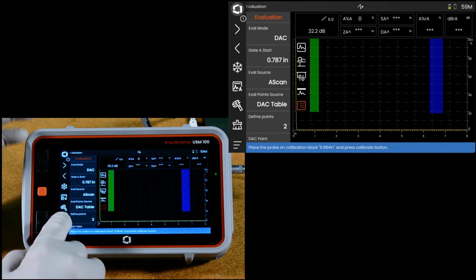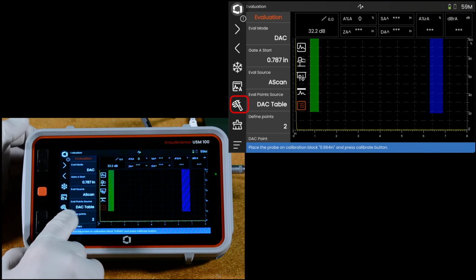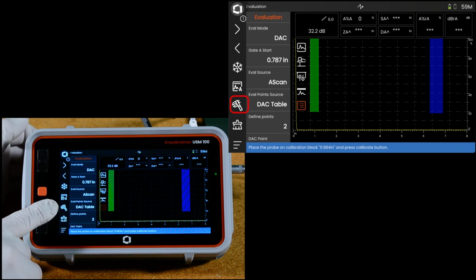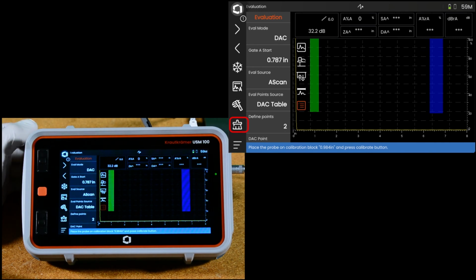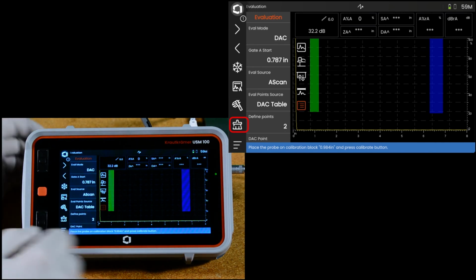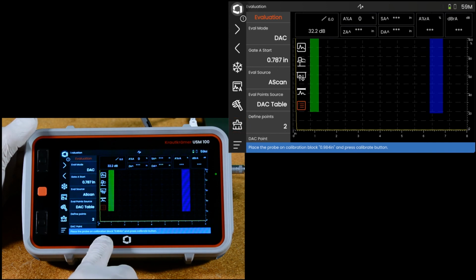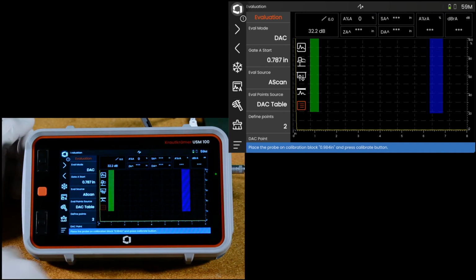You notice also over here on the command bar we got a couple of new icons. There's a little caliper icon. That is our calibrate button, and right below that is a clear. It's sort of a squeegee wiping things clear. That would clear a calibration. And you notice down here in our prompt bar, it's saying place probe on calibration block at a certain distance and press the calibrate button to start setting up our DAC.